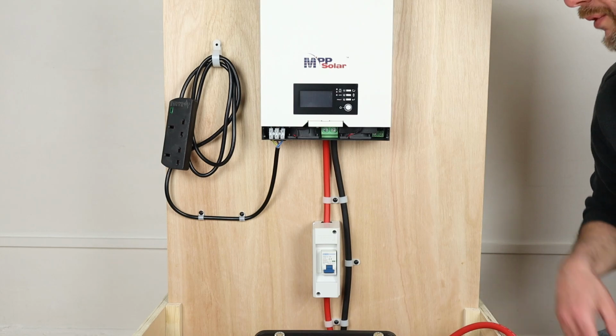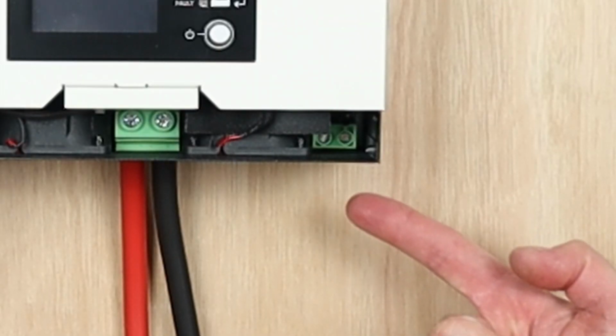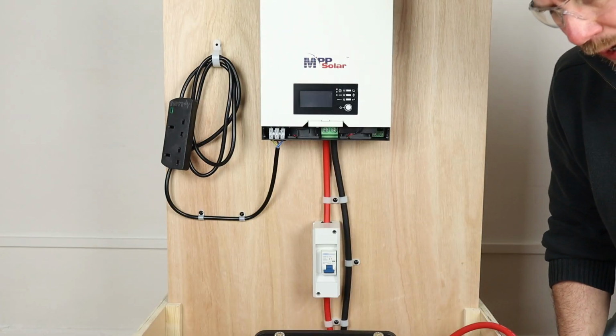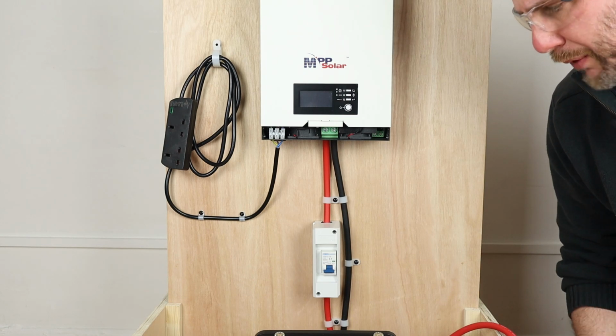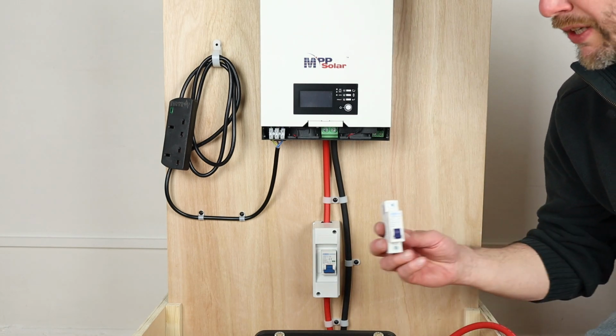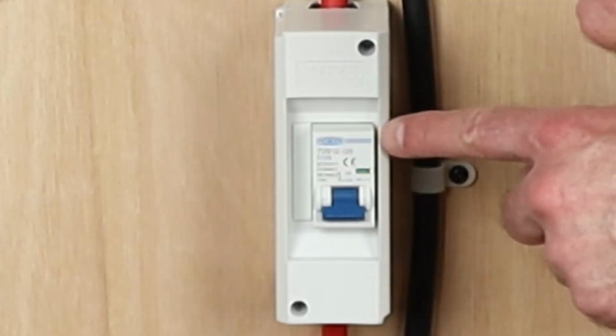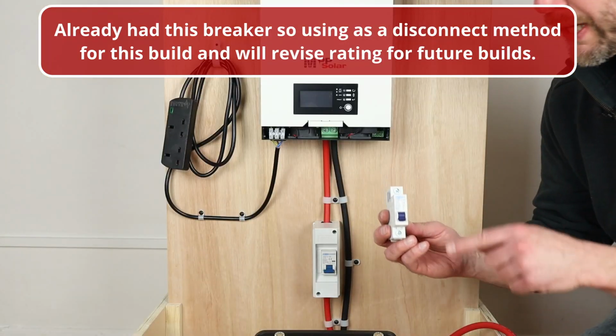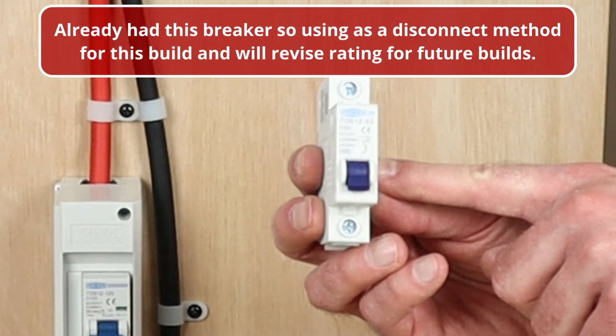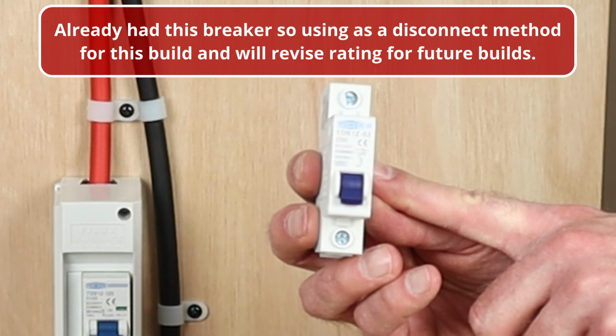Right, it's time to hook up solar now via this terminal. To do that, I'm going to be making up my own cables and connecting using a DC breaker. I've got another DC breaker here, smaller than the one we used for the battery. This one is rated up to 125 volts DC, and it must be a DC breaker, I must emphasize that. It's also rated for 50 amps.